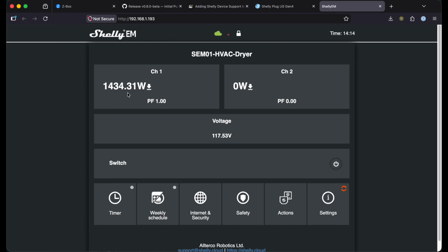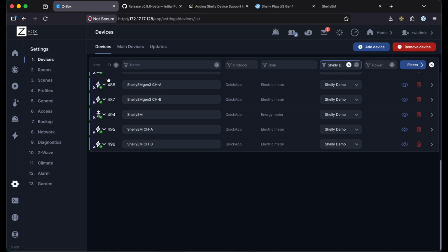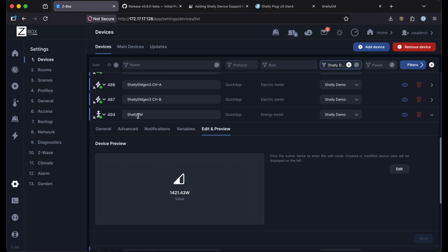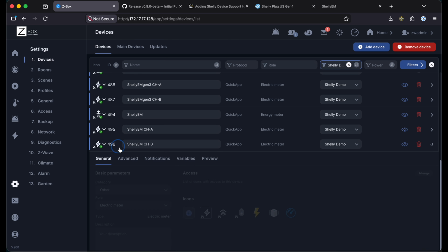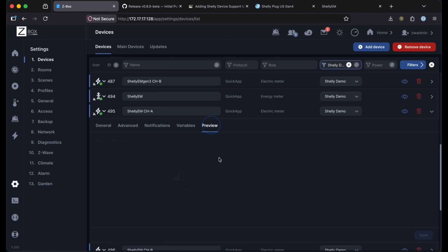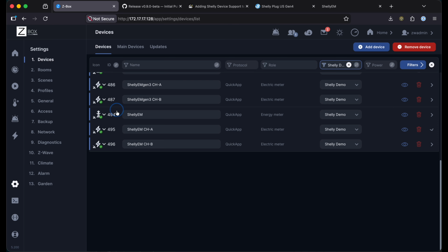So this is the outside condensing unit currently running 1425 watts. And sure enough, if we were to open up the Shelly, at the high level, you see the combination of both A and B clamps, and you'll see 1421, and that's because the B clamp is at 0, but the A clamp is at 1418.